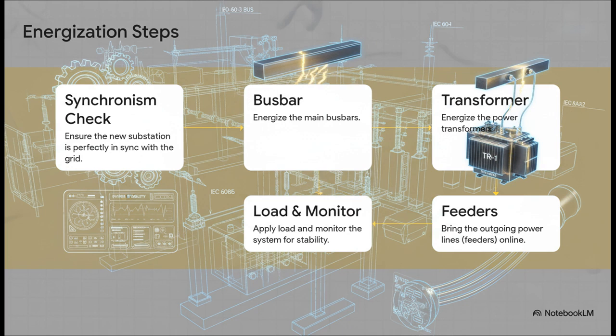First, engineers make sure the new substation is perfectly in sync with the wider grid. Then, they energize the main bus bars. After that, the power transformers come online. Then, one by one, the outgoing power lines, or feeders, are brought to life. And finally, as the station starts taking on load, the whole system is monitored like a hawk for stability.